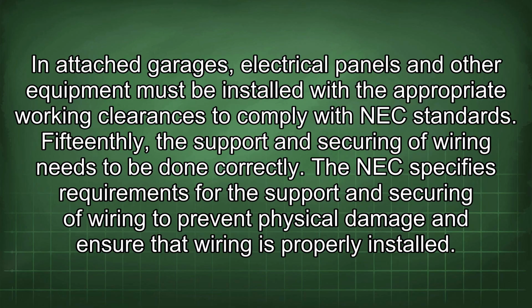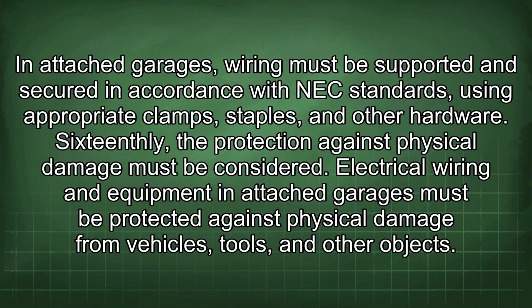15th, the support and securing of wiring needs to be done correctly. The NEC specifies requirements for the support and securing of wiring to prevent physical damage and ensure that wiring is properly installed. In attached garages, wiring must be supported and secured in accordance with NEC standards, using appropriate clamps, staples, and other hardware.